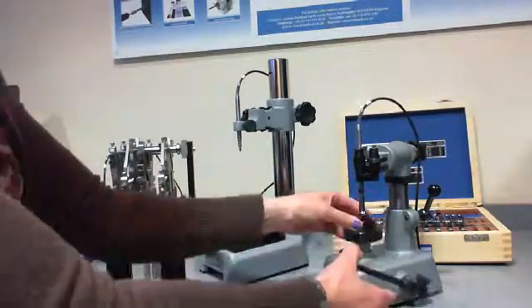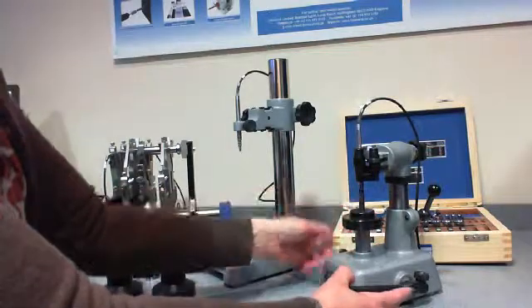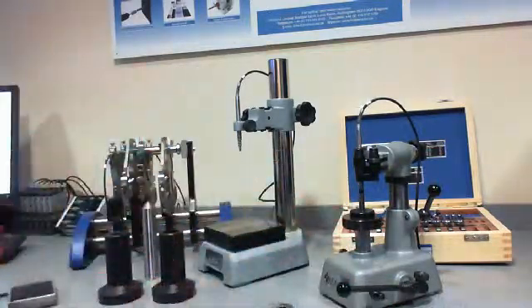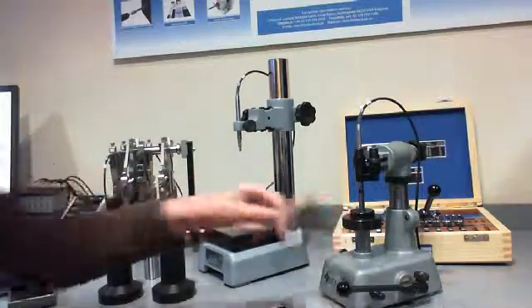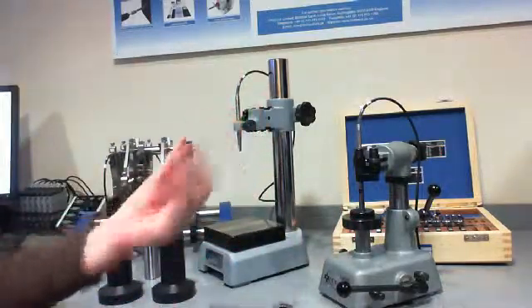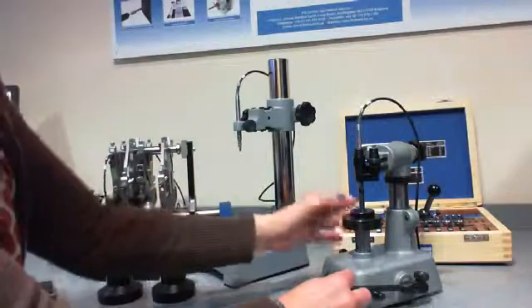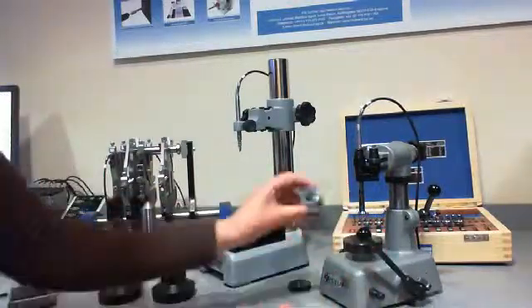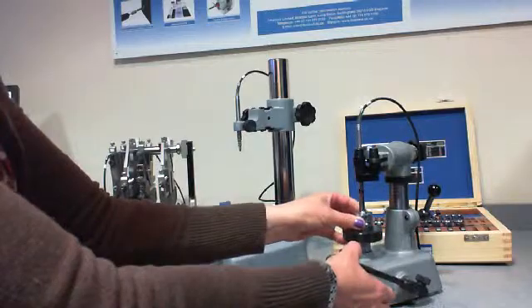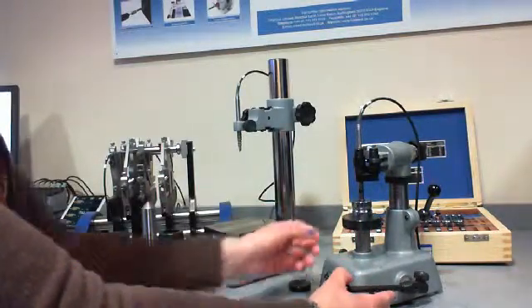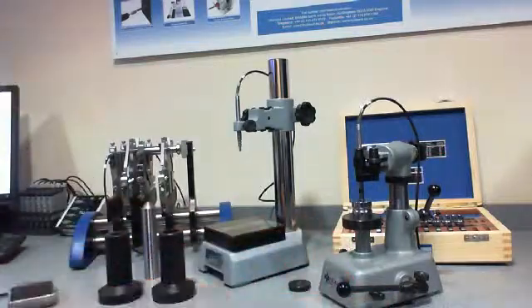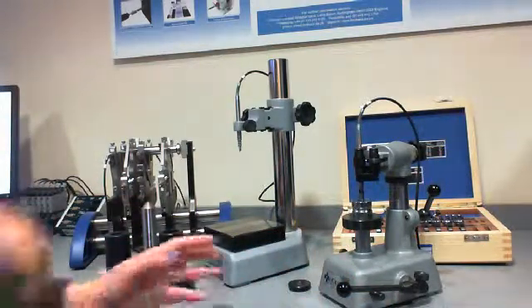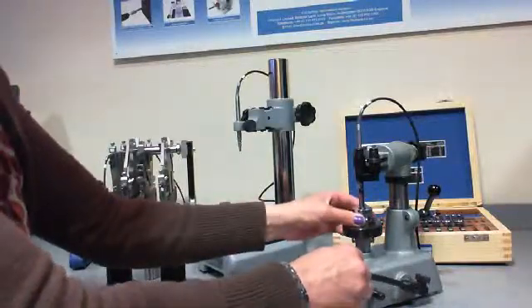So I am going to put the ring gauge in there. I am going to tell the computer that that ring gauge is 13mm so that is what the probe is looking for. And then when I am ready to measure, I put my dies on there and I move the probe through the die. When I am happy with the reading, I accept it and away we go on to the next one.